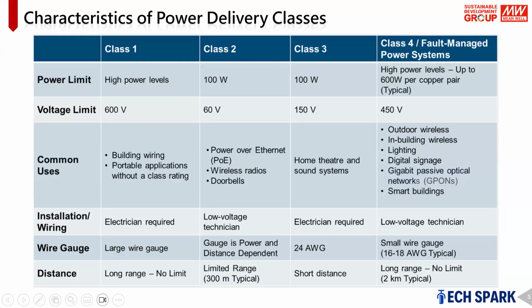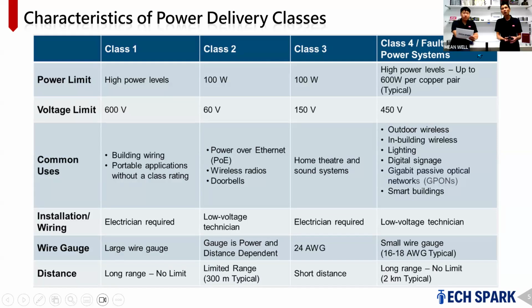Class 4 offers the same as Class 2, and it's even better, because the bus voltage can go up to 450 volts, and power transfer can go up to 600 watts per copper cable. A lot of applications now use Class 4, like PoE lighting and smart buildings. The wire gauge used has to be special wire, 16 to 18 gauge, to deliver power.